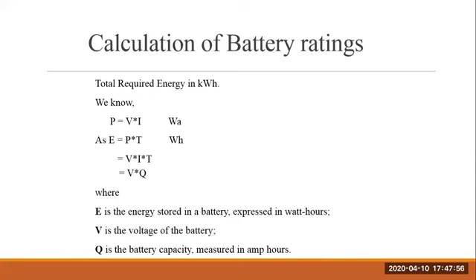Okay, we'll see one example. Required power is 3 kilowatt for 2 hours, and voltage of battery should be 48 volt. So here we have to find out ampere hour. Already we know E is equal to V into Q, so Q is equal to E by V. If we put these values, 3 into 1000 into 2 by 48, then we'll get 125 ampere hour. So here we require a 48 volt and 125 ampere hour battery pack.